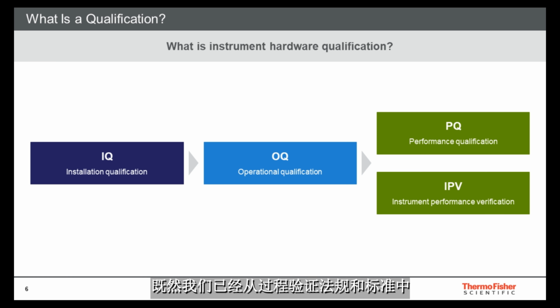Now that we have established the industry standard origin of qualification from within regulation and standards for process validation, we can move on to what a qualification is. As most of you will be familiar, there are three components to a qualification: installation, operational, and performance. Notice an additional chevron below PQ on this slide. Here is where Thermo Fisher Scientific Life Sciences Group differentiates its RUO, or research use only, and IVD, or in vitro diagnostic, DX branded instrument products.